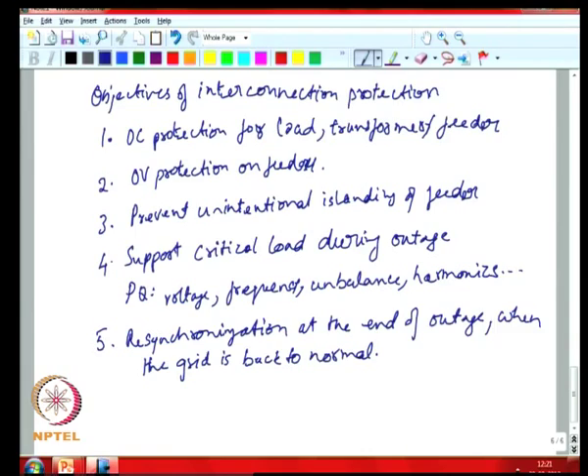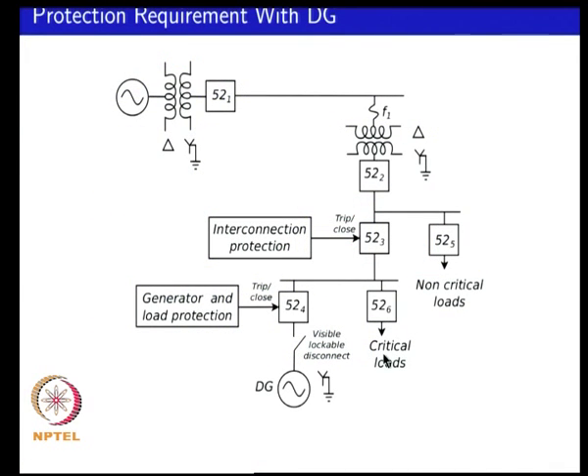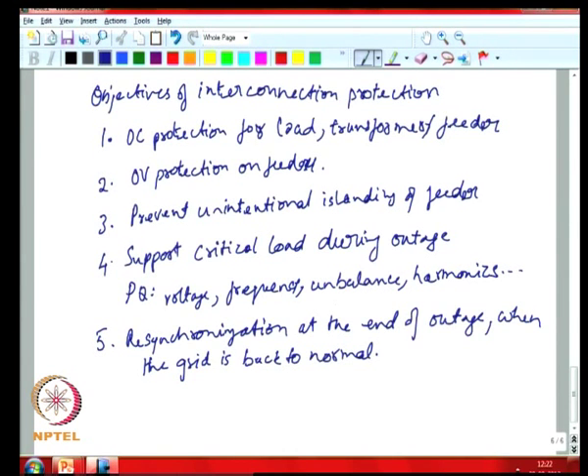You might also have a requirement for reenergizing a dead bus. If the whole system is dead and the breaker is open, you need to monitor voltages to ensure it is a dead bus. If everything is dead you can reenergize your critical loads, as long as you are not reenergizing a connected or non-functional DG. You do not want to start up a large machine or inverter when it is still connected and not supposed to function. Dead bus restarting with appropriate logic would also be required.